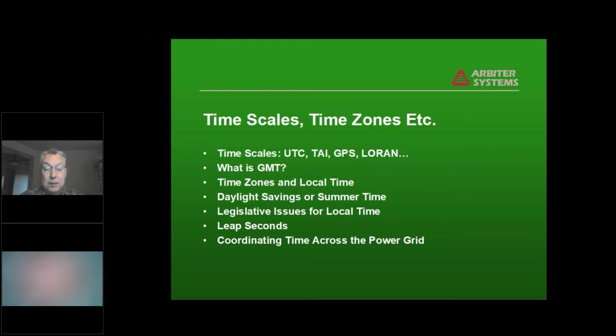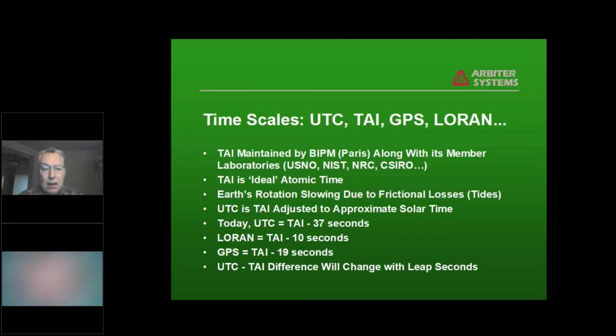And the other thing is when daylight savings time changes or when a leap second happens, there's often a period of time where there's some uncertainty between all the different IEDs. Different locations taking different amounts of time to adjust to the changeover can result in lots of problems with keeping things synchronized. So we've got different time scales in the world.